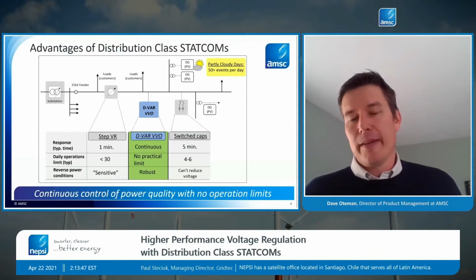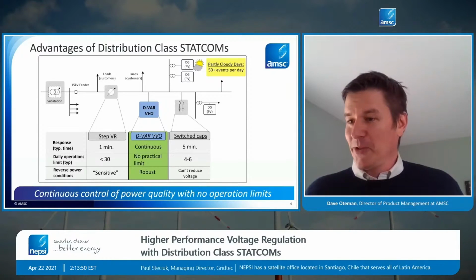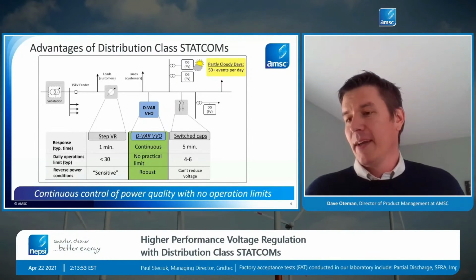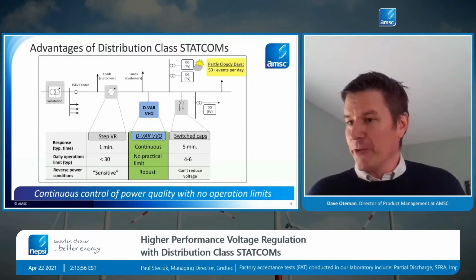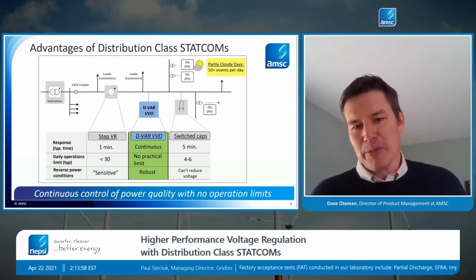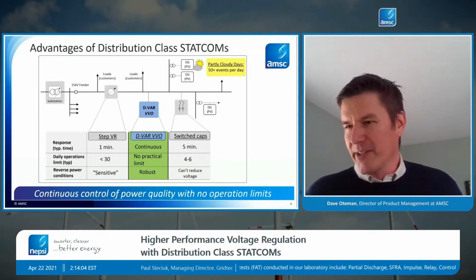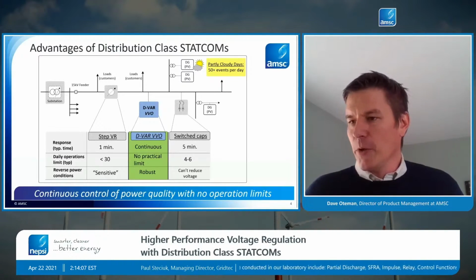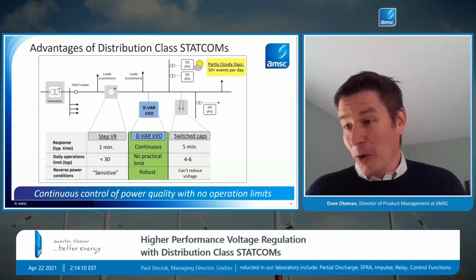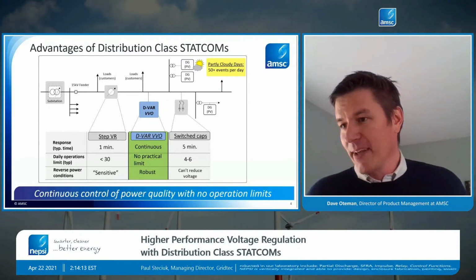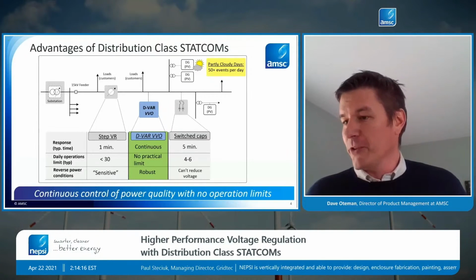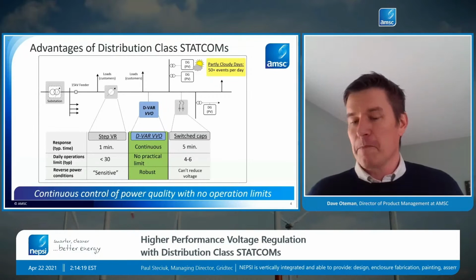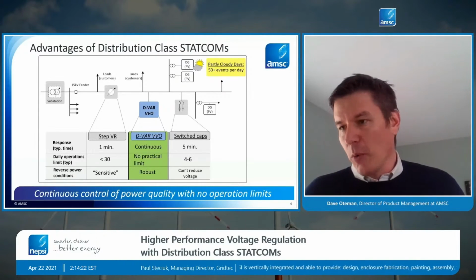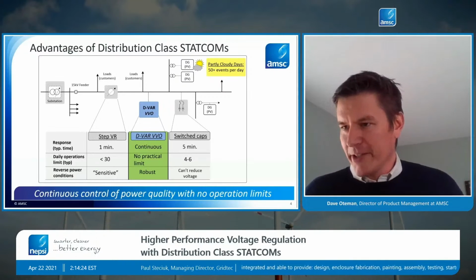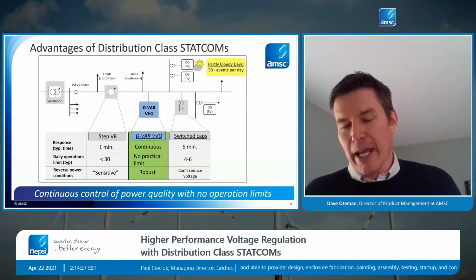So that's really something that the distribution system was not built out to support. And the traditional technologies that are managing average voltage were not built out to support that. So I'm just showing a little summary quickly here. Switch caps typically switch 4 to 6 times a day in order to prevent power quality problems. When a switch cap switches, it causes a step change in voltage, so most utilities limit their operation just for that reason alone. In addition, the mechanical switch will wear out if they operate too much. So most utilities are in that 4 to 6 operations per day limit.